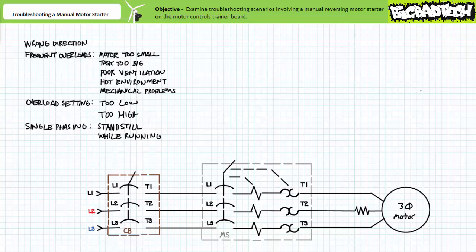Although not as extreme as complete loss of a single phase, consider a slightly imbalanced three phase AC system where the magnitude of one phase as perceived by the motor is different than the other two due to a poor connection. In this scenario, there would be a voltage drop across the poor connection as if a series resistor was included in the circuit. Imbalance occurs, however, it's not as significant as complete loss of a single phase. Depending on the magnitude and duration, this scenario too may result in an eventual overload. Again, ammeter, voltmeter, and ohmmeter checks would identify which phase is suspect or where exactly the poor connection exists.